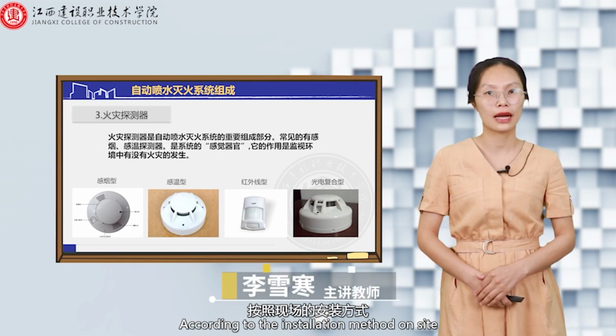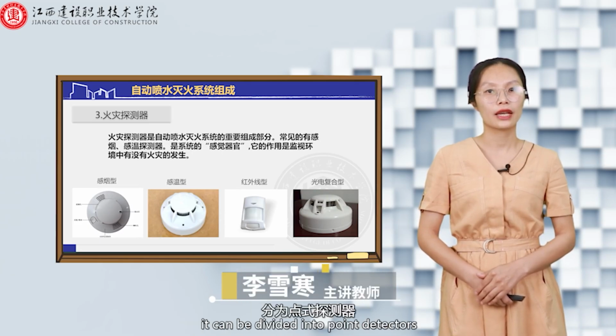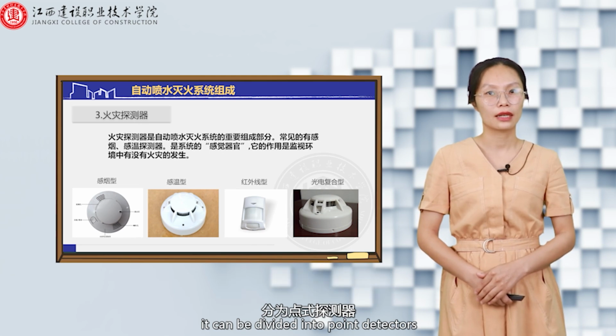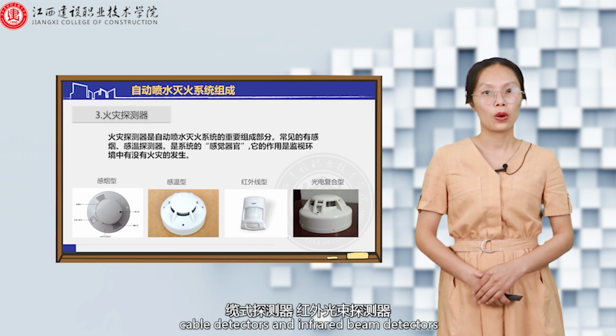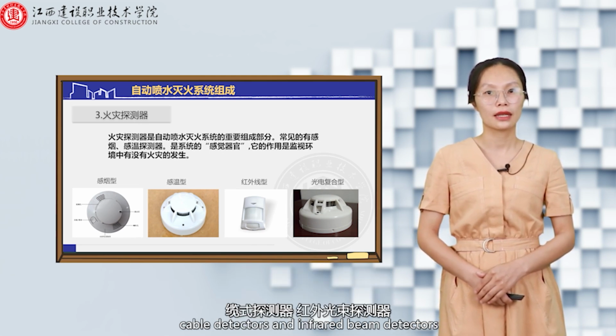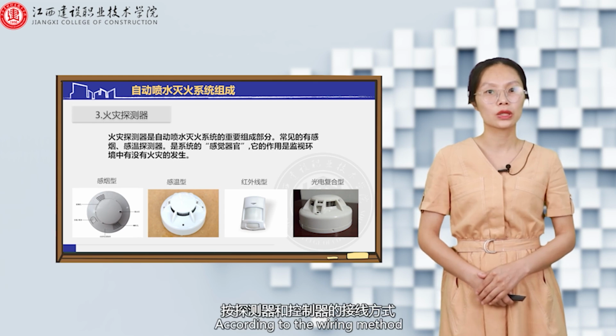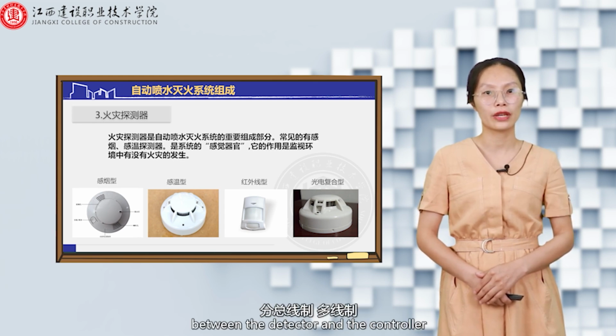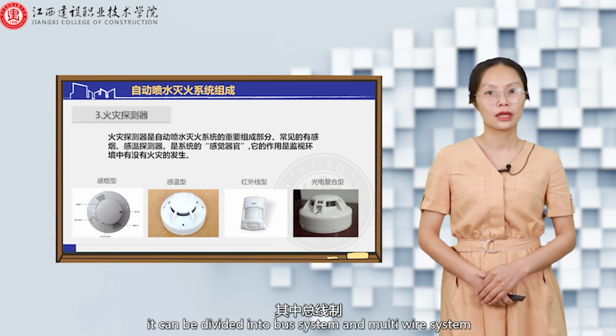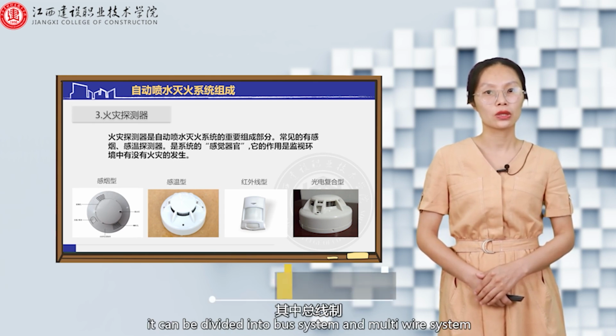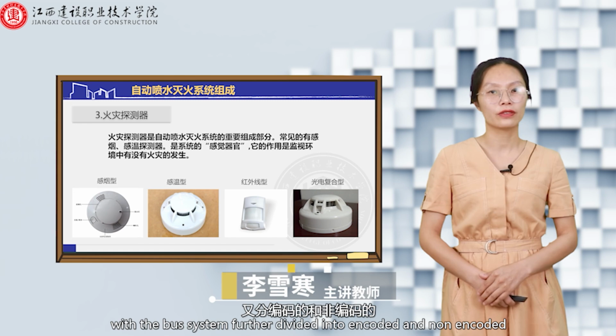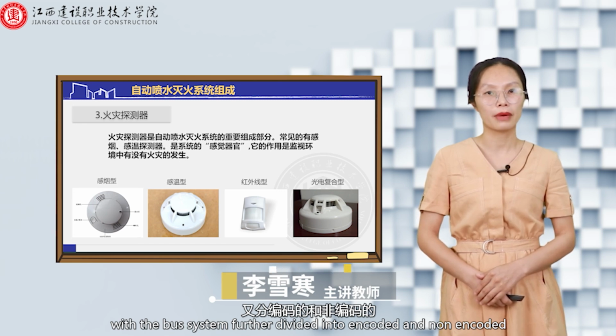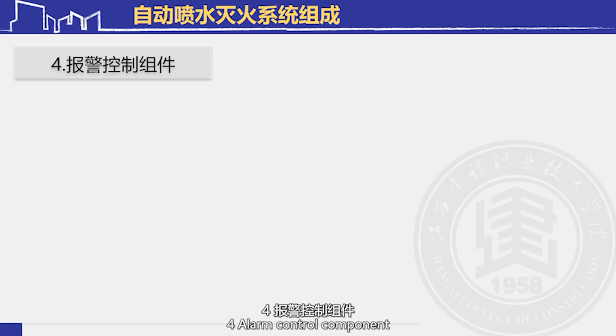According to the installation method on site, it can be divided into point detectors, cable detectors, and infrared beam detectors. According to the wiring method, between the detector and the controller, it can be divided into bus system and multi-wire system, with the bus system further divided into encoded and non-encoded. Fourth, alarm control component. 1.